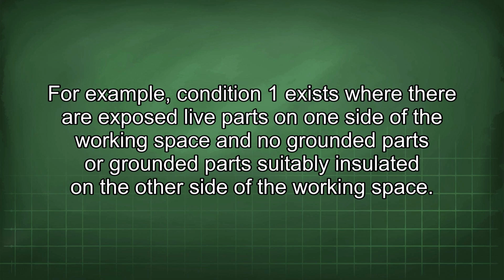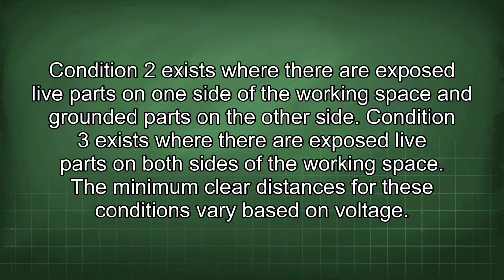For example, Condition 1 exists where there are exposed live parts on one side of the working space and no grounded parts, or grounded parts suitably insulated, on the other side of the working space. Condition 2 exists where there are exposed live parts on one side of the working space and grounded parts on the other side. Condition 3 exists where there are exposed live parts on both sides of the working space. The minimum clear distances for these conditions vary based on voltage.